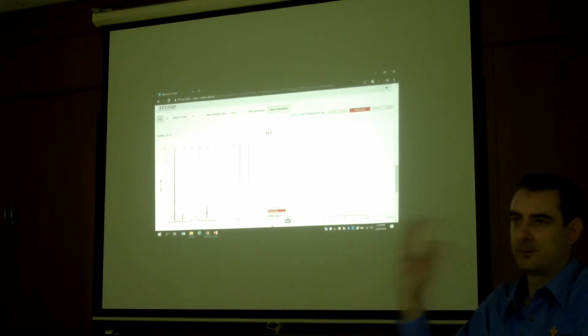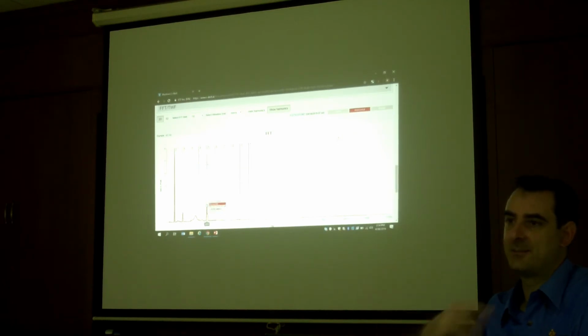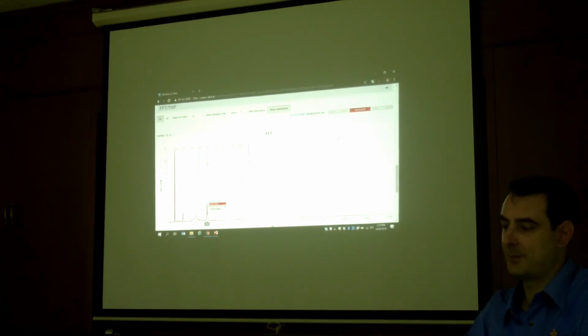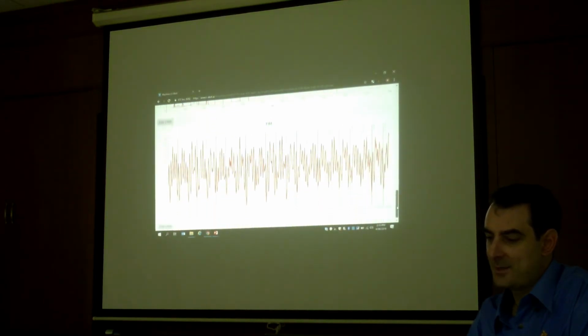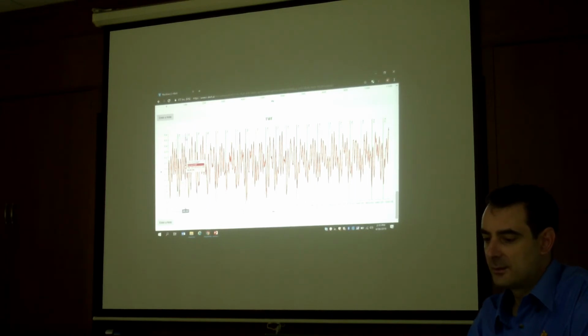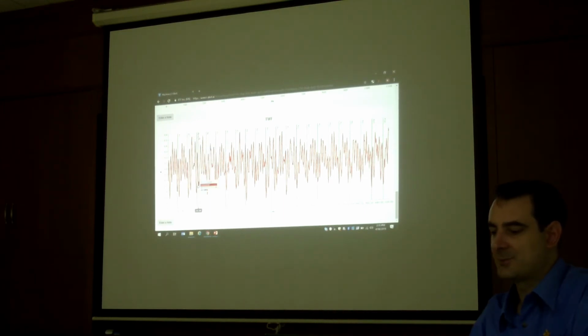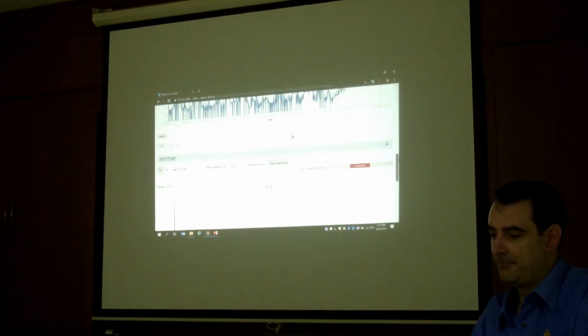So we know that all those peaks are happening at the same frequency as the revolutions, but just multiples. So 1 times the revolution, 5 times the revolution. So this is a 5-vane pump. So every time the impeller spins 1 time, it passes the cut water 5 times. That causes a little vibration. So again, that's 1.22, that's not too bad. So the vibration peak is happening at the 1 times. If I scroll down, I can see the time waveform, and the rotations are there. So this is 1 rotation, 2 rotation, 3 rotation over the time. So this helps the vibration analyst determine what's going on.